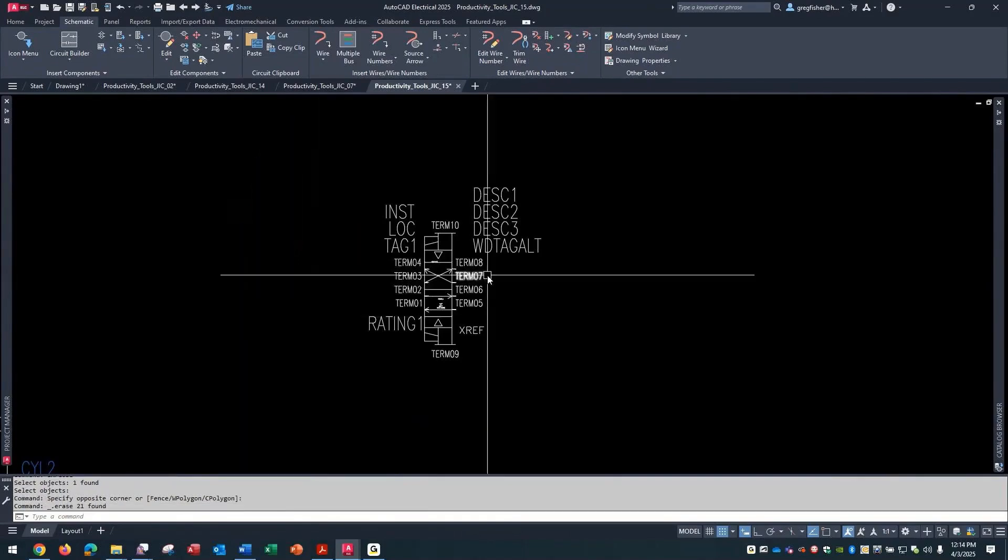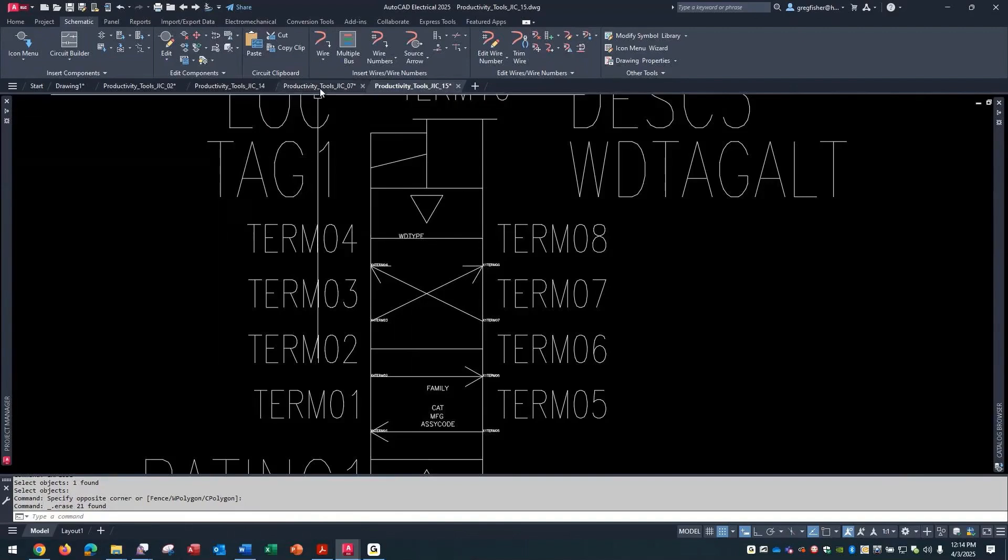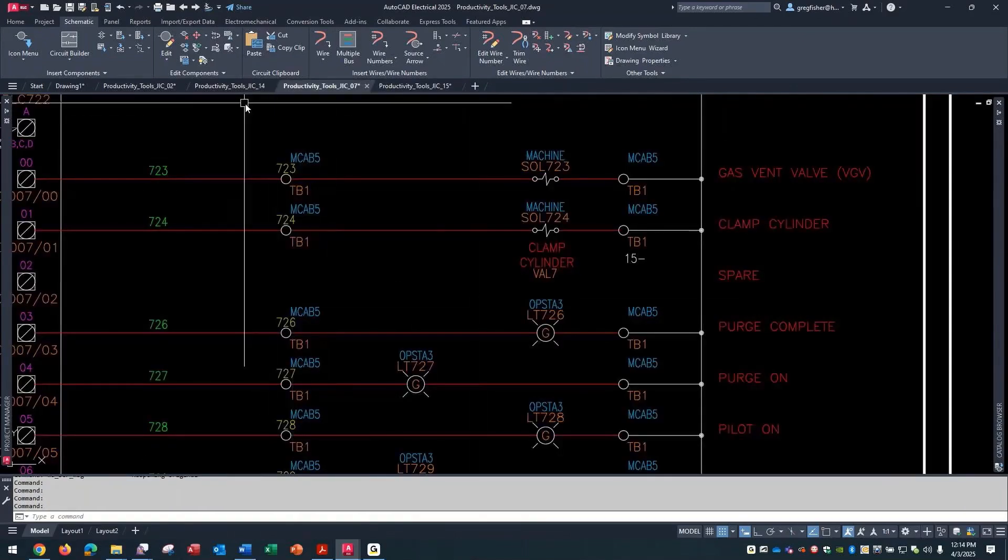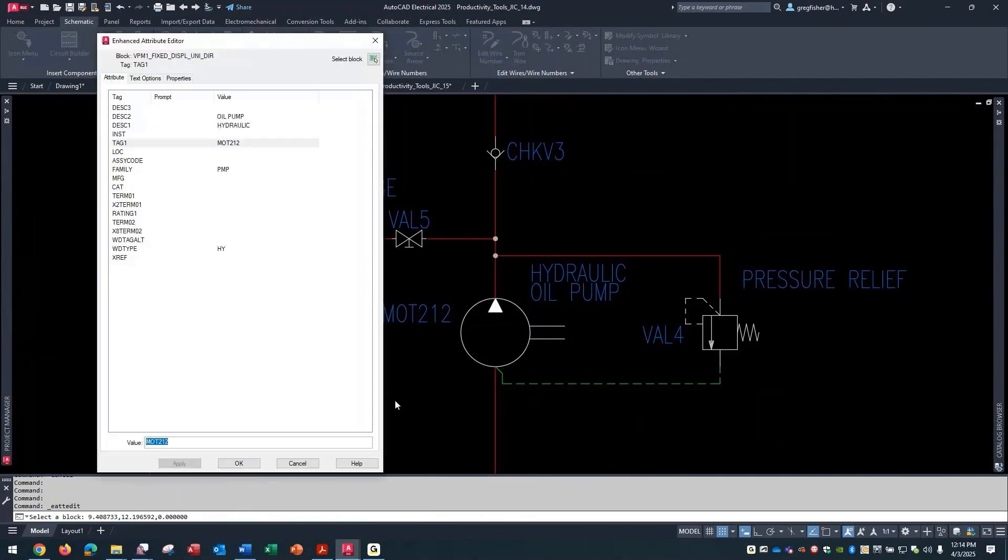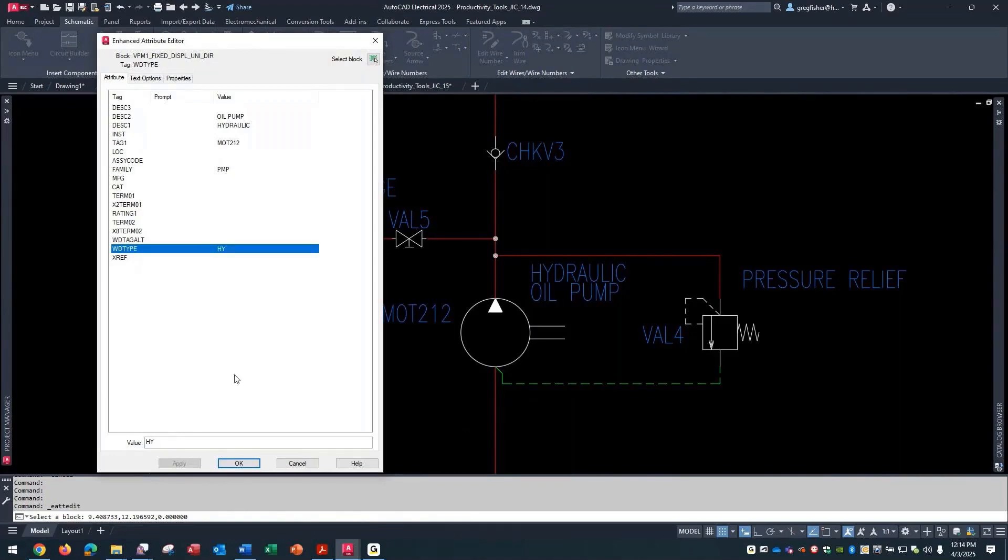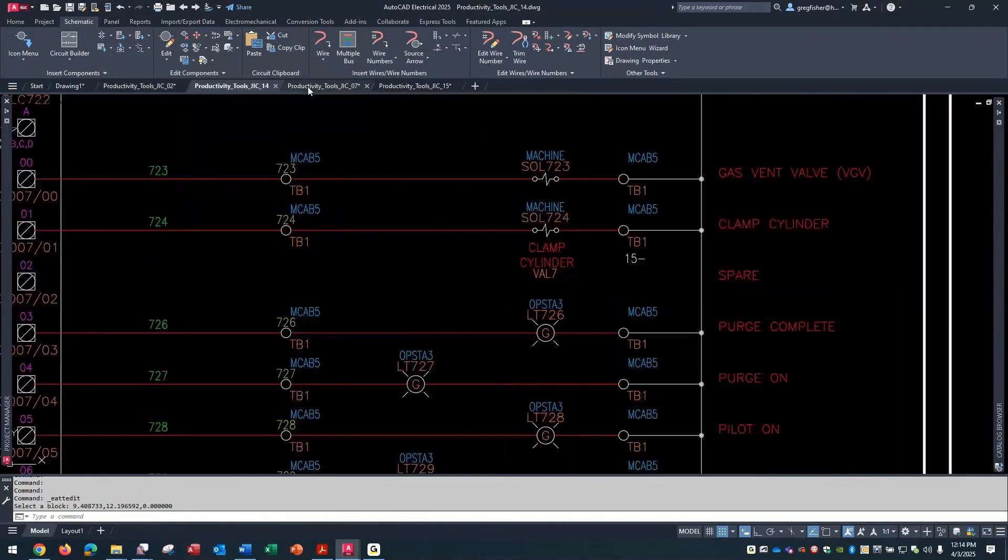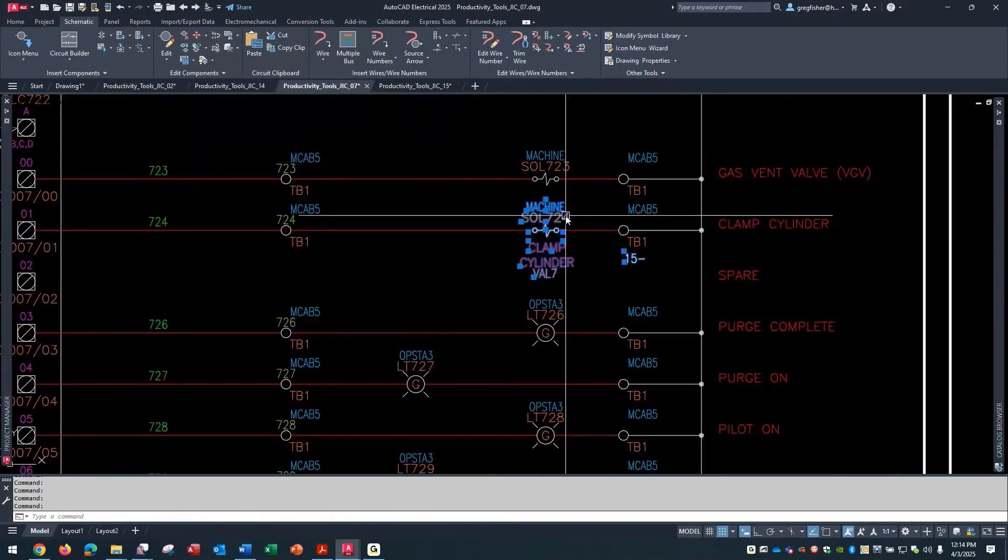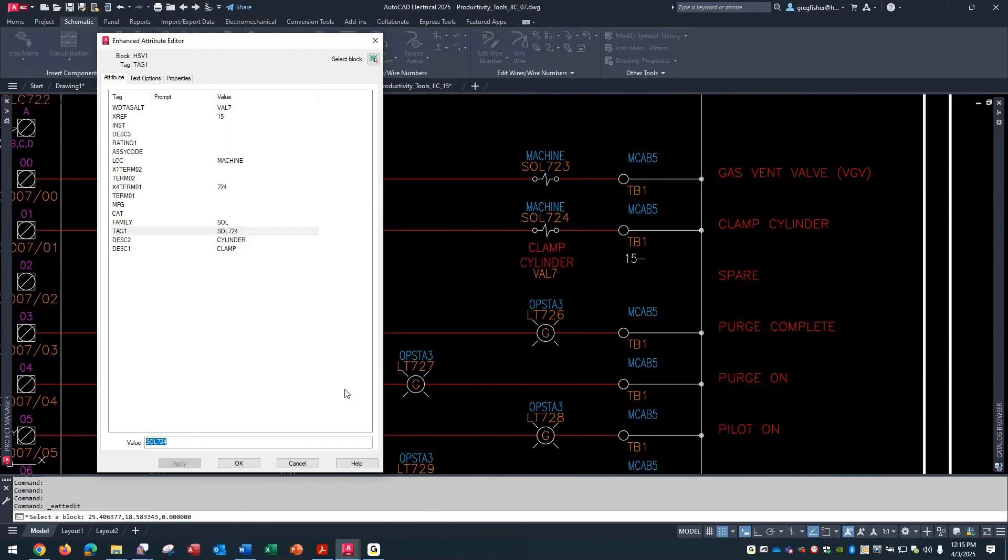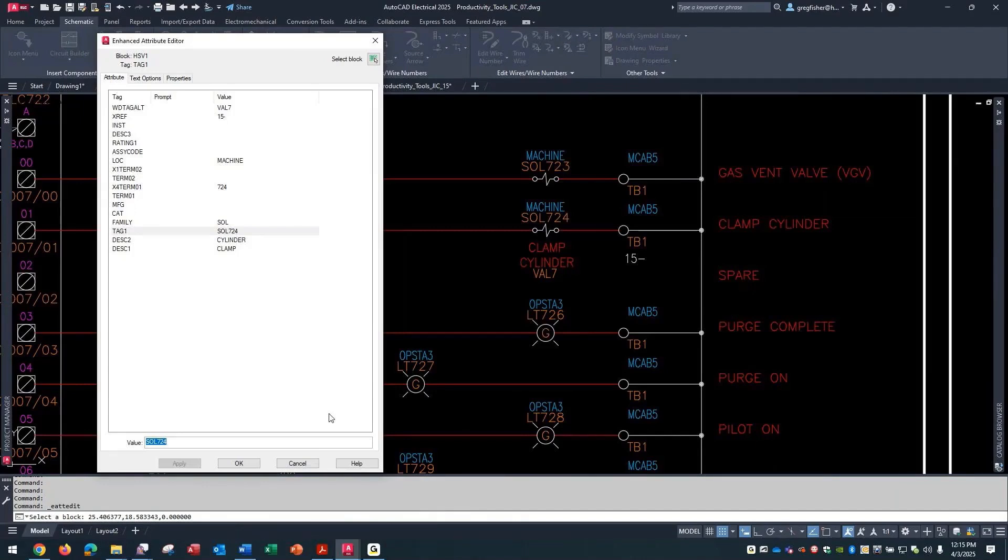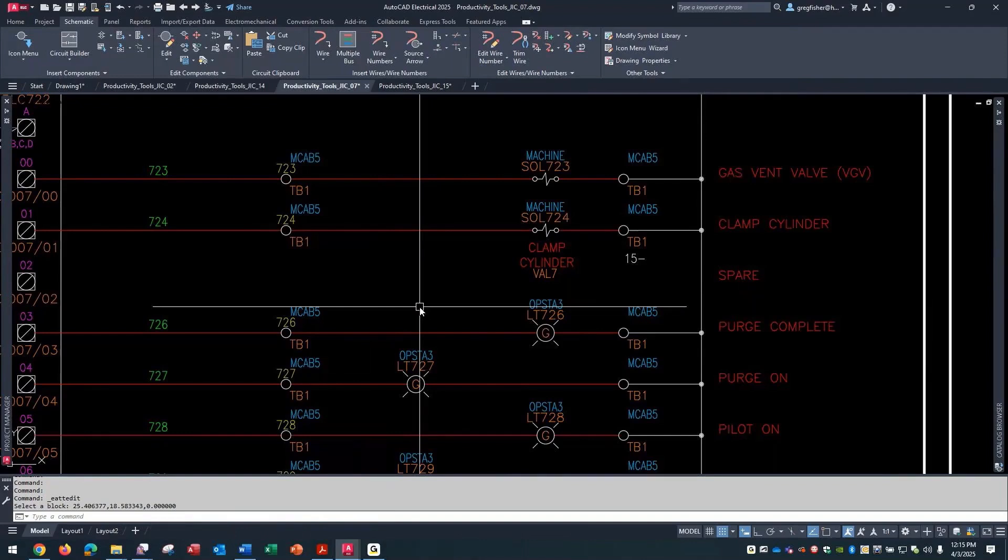It's all about the WD tag and the WD type. No different. On this one right here, there's your WD tag, there's your WDT. Now, on a symbol like this one, all it has is the WD tag. When I'm creating a symbol for peer-to-peer, I just include both automatically. That way you don't have to worry about anything missing. Always have the WD type and the WD tag alt attributes whenever you create a custom symbol that you want to have the ability to go peer-to-peer on. Just add them.